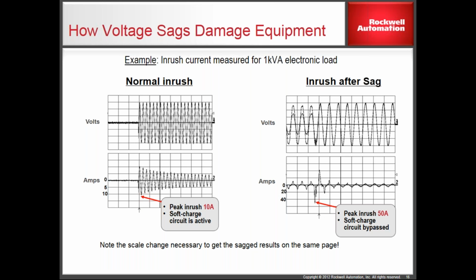This is a picture of what that looks like. This is normal inrush current on the left, the peak right at the beginning as you'd expect at startup, then the current is well managed down to a steady state. Same circuit here, but we have a voltage sag, and you can see where the sag ends. Just at the end of the sag, we had to change the scale, the peak inrush current hit 50 amps. And this is the most conservative view of this problem.